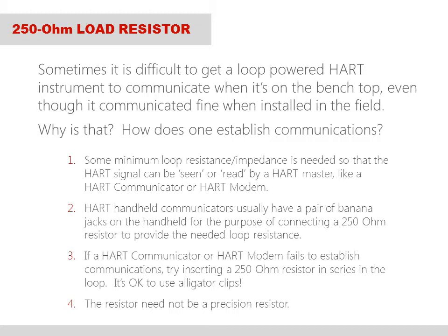Sometimes it is difficult to get the HART device to communicate when it's on the benchtop, even though it communicated fine when wired in the field. Oftentimes, when the HART instrument is on the benchtop, the loop does not have enough resistance for the HART signal to be seen by the HART master. Therefore, a minimum loop resistance is needed so that the HART signal can be seen or read by a HART master, such as a HART communicator or HART modem.